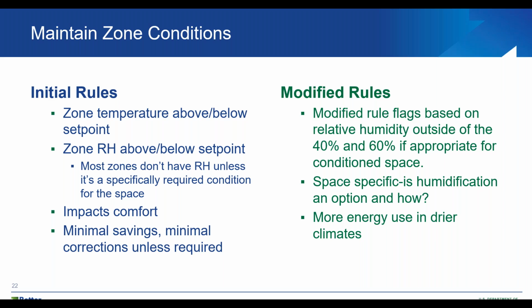So I'm going to talk a little bit about maintaining zone conditions. Again, it's not necessarily recommending or not recommending, but in some environments, the advantage of having FDD through the building automation system is you get to monitor the entire system. So you're looking at pretty much every point in the building automation system, which means every zone. So you can monitor zone temperatures, zone relative humidities, have comfort impacts noted. Each individual one may not have a lot of savings, but you can look directly and find out which zones have which problems.